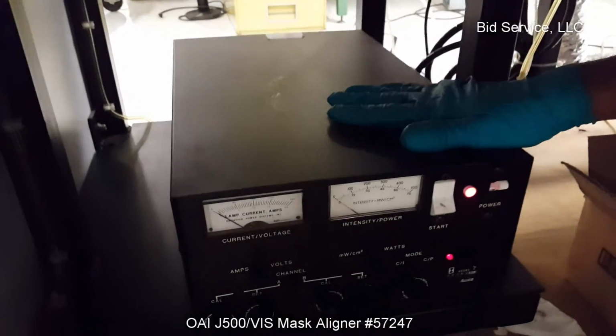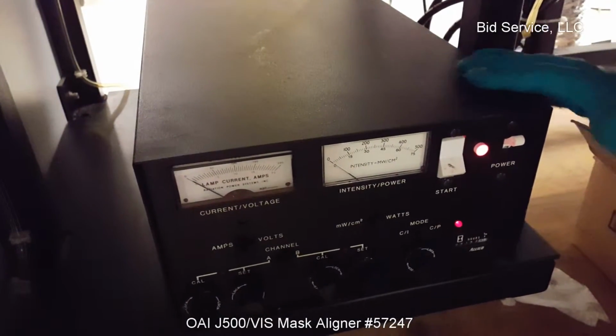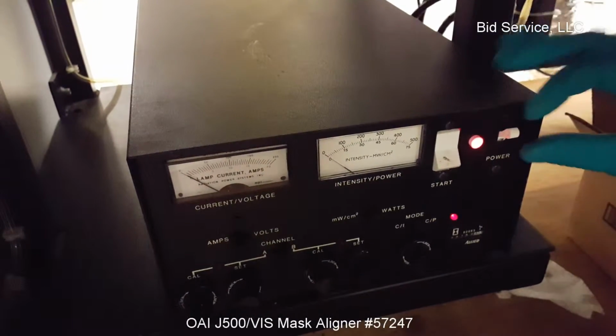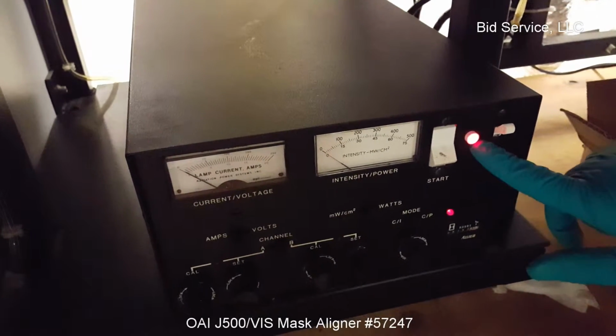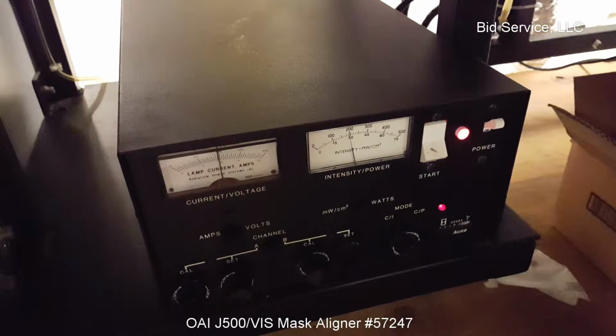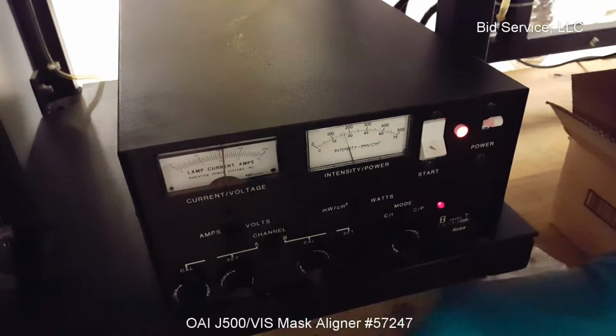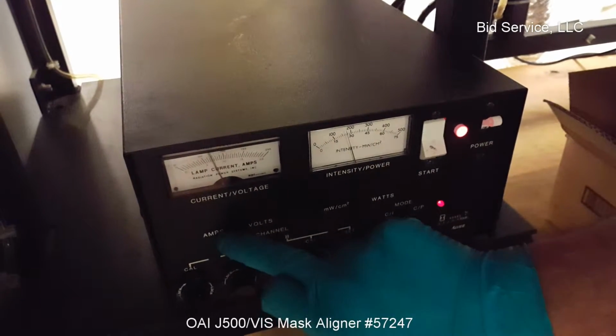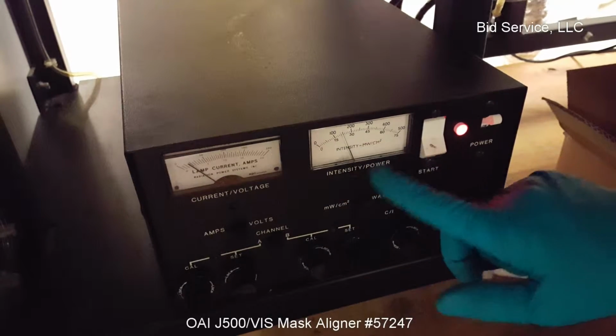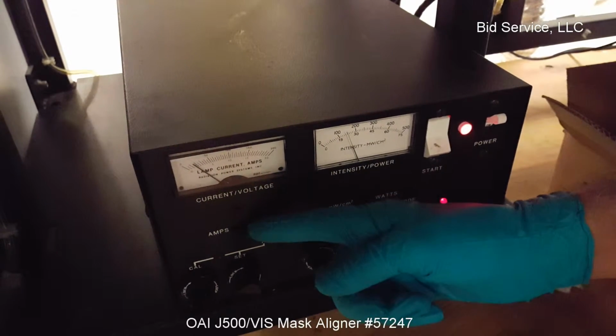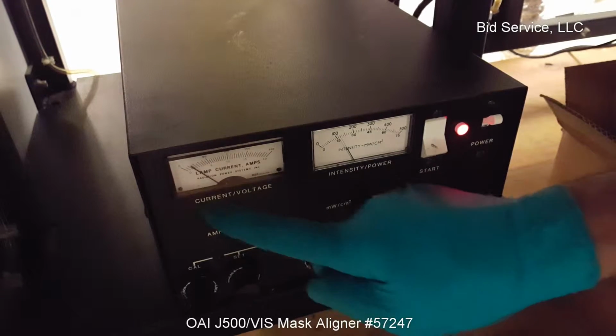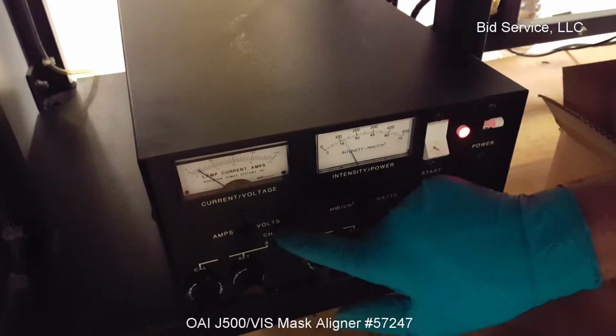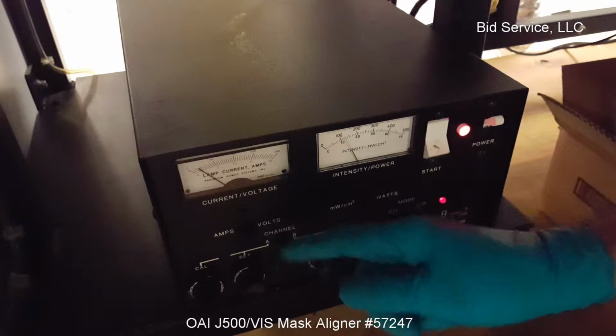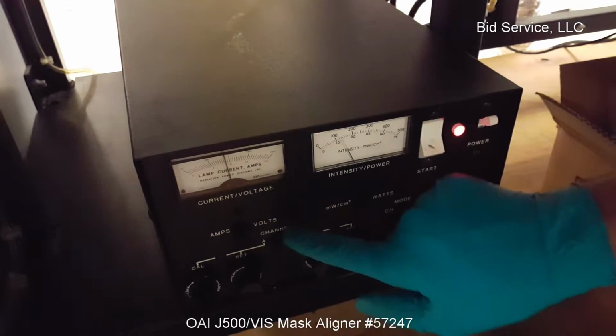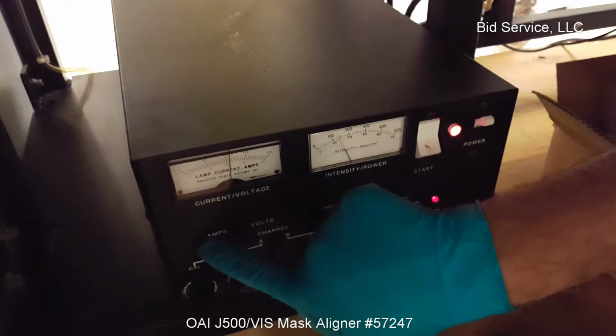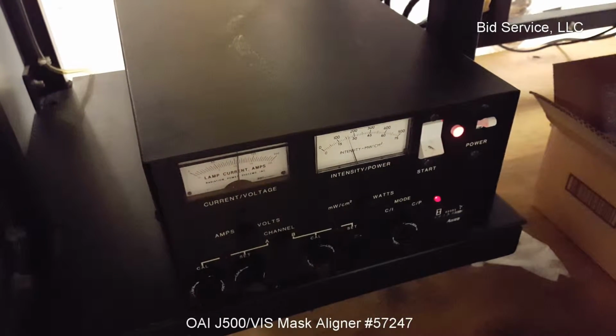Here is the arc lamp power supply. On power up, these LEDs will turn on, that's the power indication. And I'm turning on the lamp. It'll take about 10 to 15 minutes for the lamp to stabilize. So the initial voltage will be low, but as the lamp heats up and the current and voltage levels stabilize, the voltage level will increase and the current will decrease.